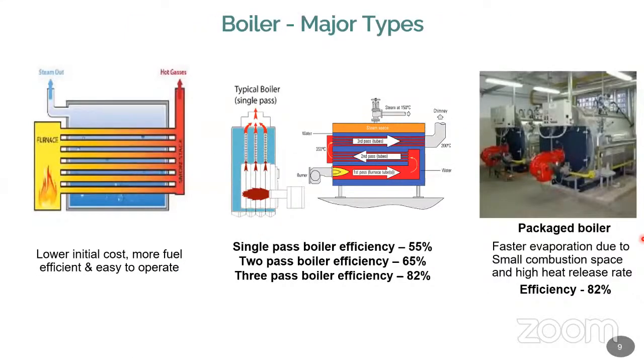Okay. Now you can see the boiler structure and how steam can be produced. I already told you that we have a fire tube boiler or a water tube boiler. Basically, you have a single pass, two pass, or even three pass. Normally 3-pass boilers are used. I mean, 3 different ways are available to flow your water, or the fuel, sorry, or the fire. If it is a fire tube boiler, it means the fire will go through 3 tubes, or if it's a water tube boiler, the water will flow through three tubes. So basically, based on the passes, the capacity will increase.